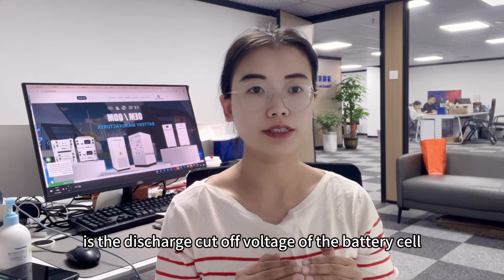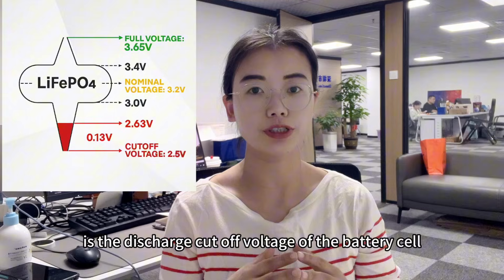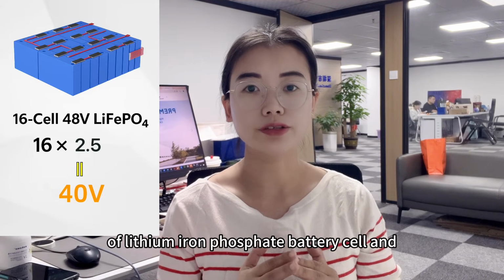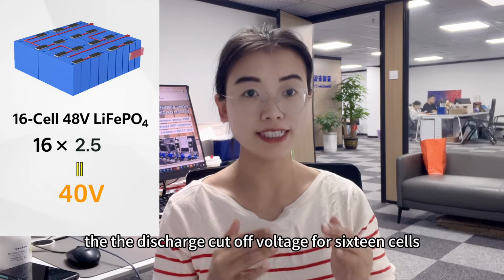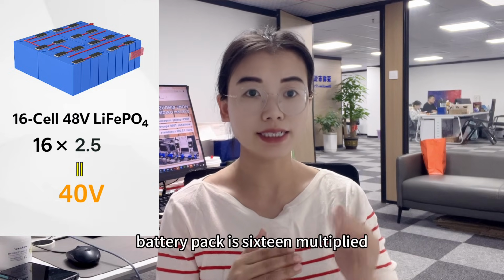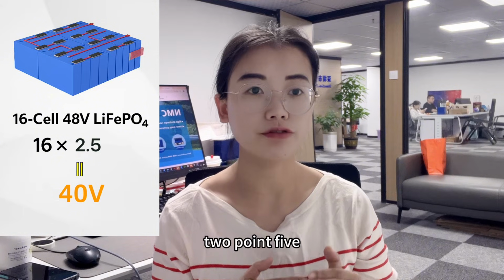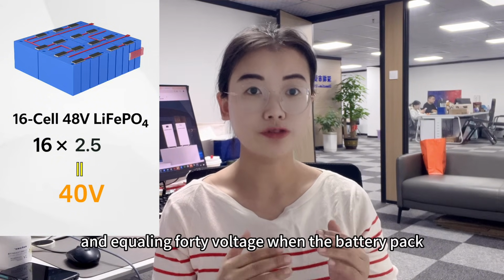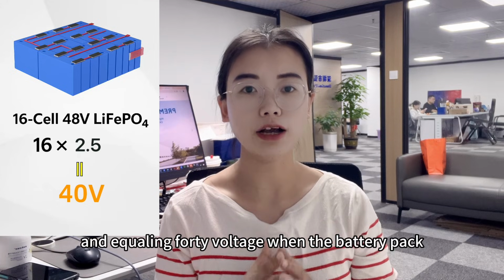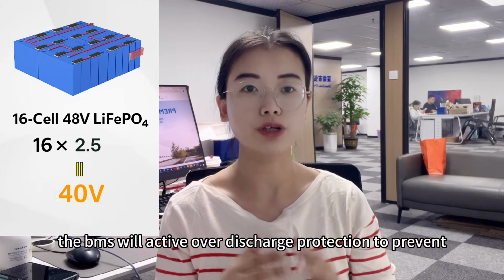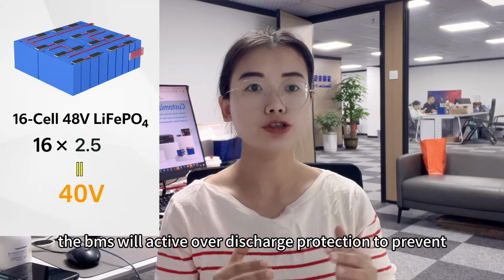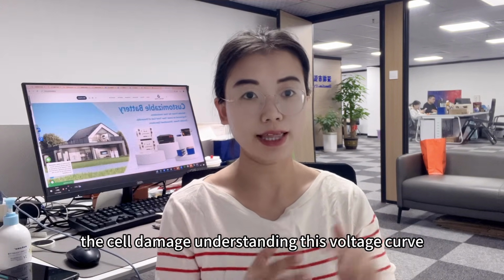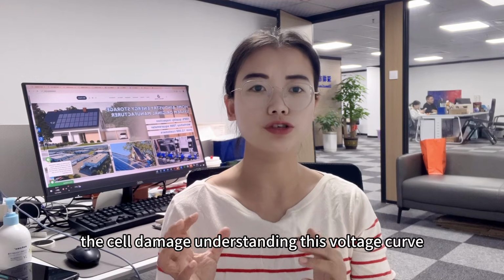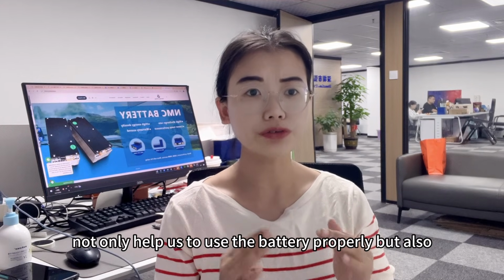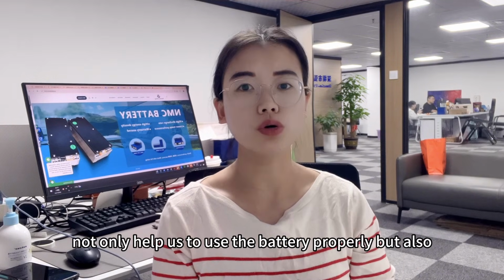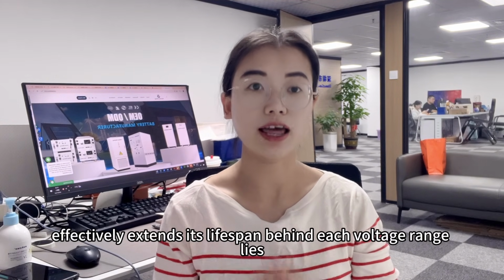2.5 volts is the discharge cutoff voltage of the lithium iron phosphate battery cell. The discharge cutoff voltage for a 16-cell battery pack is 16 multiplied by 2.5 volts, equaling 40 volts. When the battery pack voltage drops to this value, the BMS will activate over-discharge protection to prevent cell damage. Understanding this voltage curve not only helps us use the battery properly but also effectively extends its lifespan.